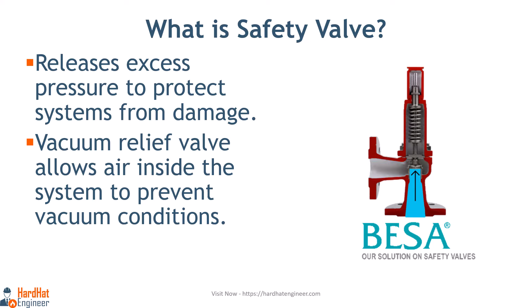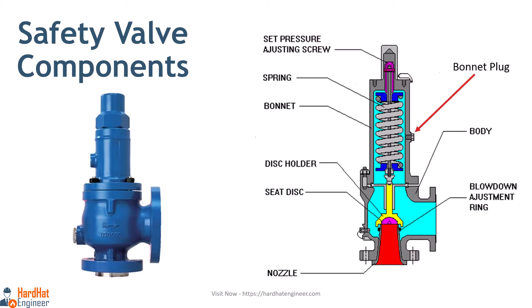What is a safety valve? Safety valves release excess pressure to protect systems from damage, making them crucial for maintaining safety in pressure vessels and other equipment. The primary purpose of a pressure relief valve is to protect life and property by venting fluid from an over-pressurized system. The vacuum relief valve ensures that a vacuum-like situation does not occur by allowing air inside the system. There are three types of pressure relief devices: reclosing type, non-reclosing type, and vacuum relief devices.